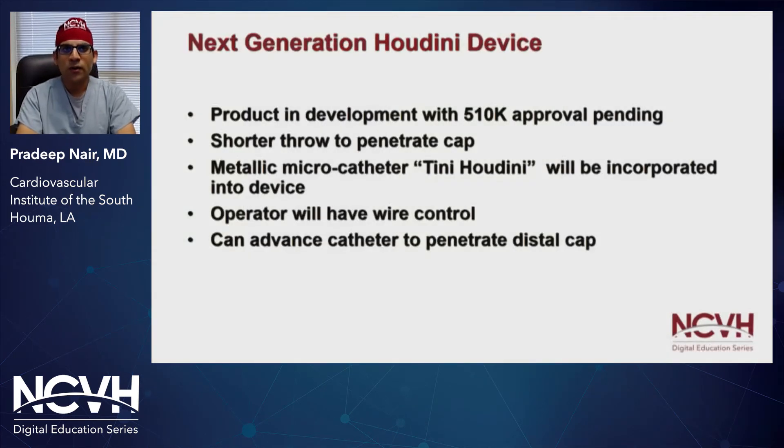There is a new generation of the Houdini device in development that is pending 510k approval. The beauty of this newer device is its shorter throw to help penetrate caps more efficiently. There's a metallic micro catheter, which they have termed the 'Tini Houdini,' which will be incorporated into the device, where the operator will have full control of the wire throughout the procedure. You can advance the catheter all the way towards the distal cap if necessary.